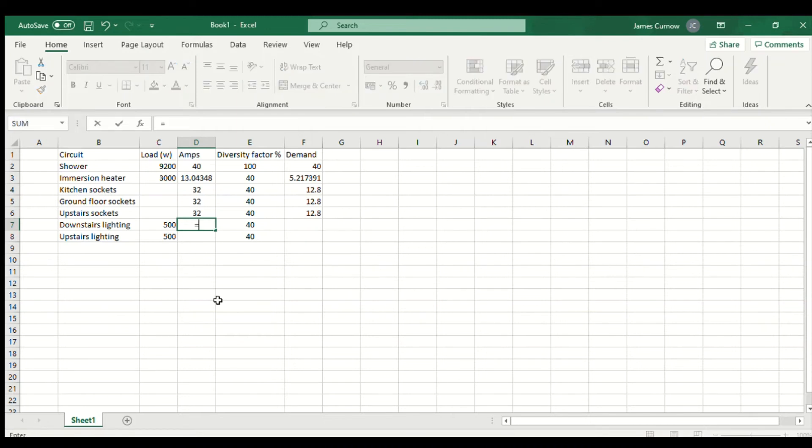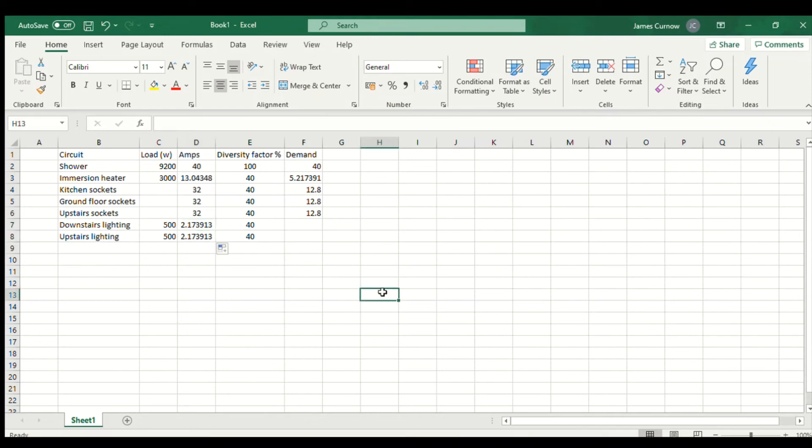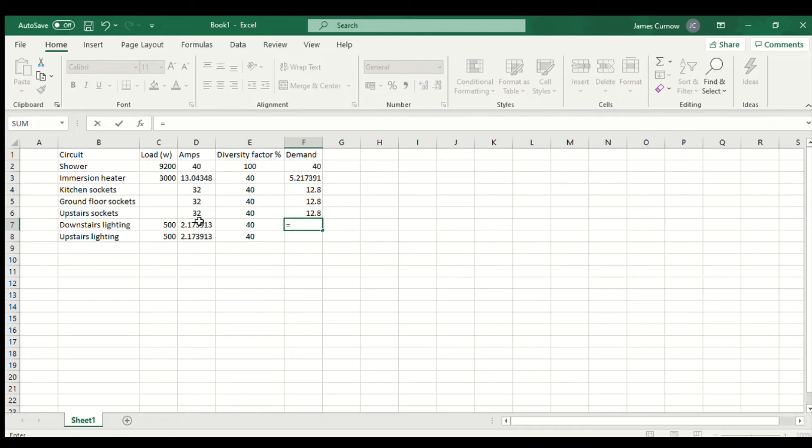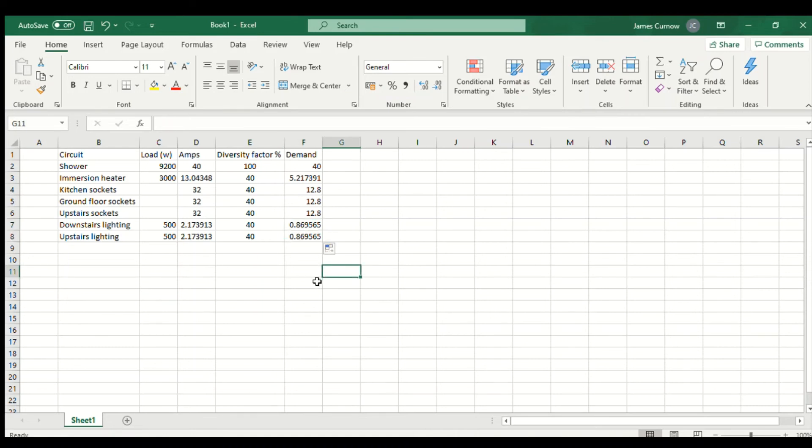For the remaining two circuits it's the same formula but because the wattage is over here, I'm going to do the design current first. So equals wattage divided by 230, copy that down, and then equals asterisk for multiply and then 0.4. That gives us 40% of those two.